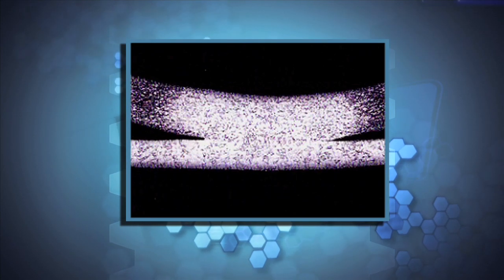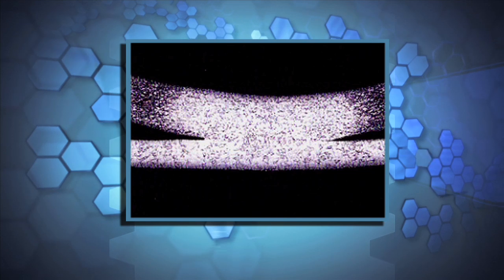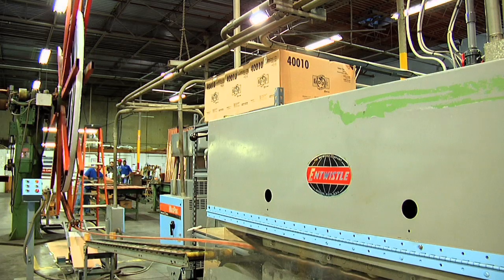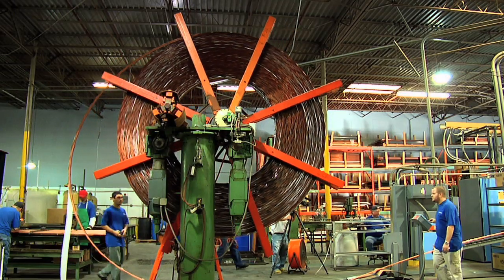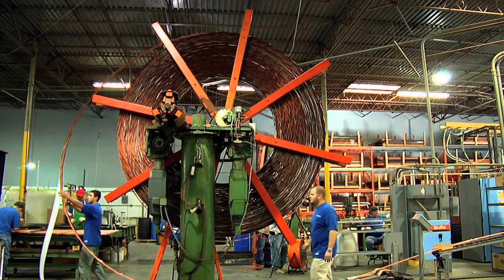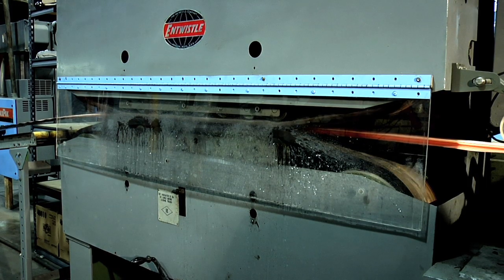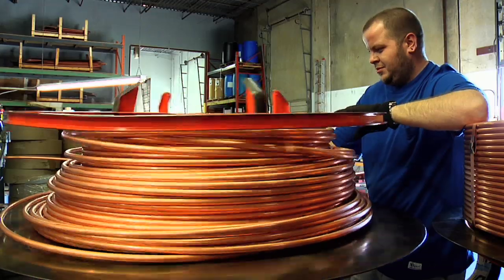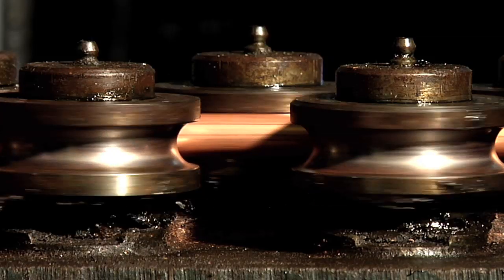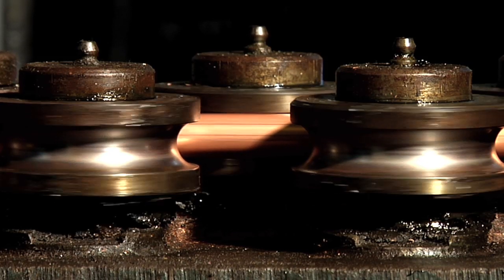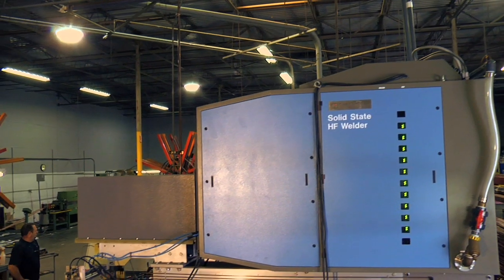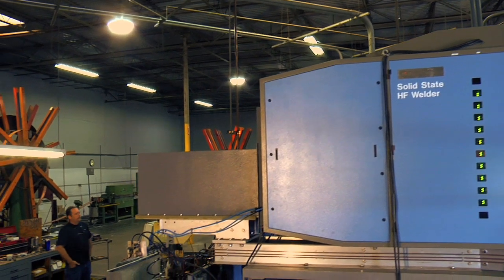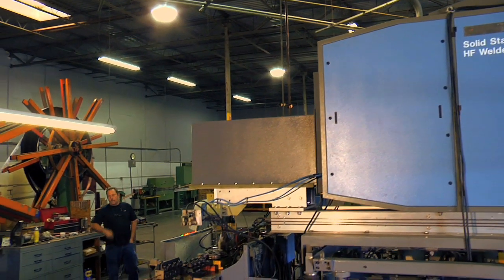Cross-sectional microanalysis shows grain structure throughout the weld zone without fractures or inclusions. The weld line consists of dual take-up towers powered by DC drives and controlled by a dancer servo to receive the 16-foot diameter rolls of welded product. A caterpillar drive section pulls the material through the weld head from the feed reels at the front of the machine. Straightening and shaping rolls precondition the tube for welding, while a set of reversing rolls apply proper tension to the fin. Power to the material is provided through the overhead conduit, which is encased in an aluminum guideway.